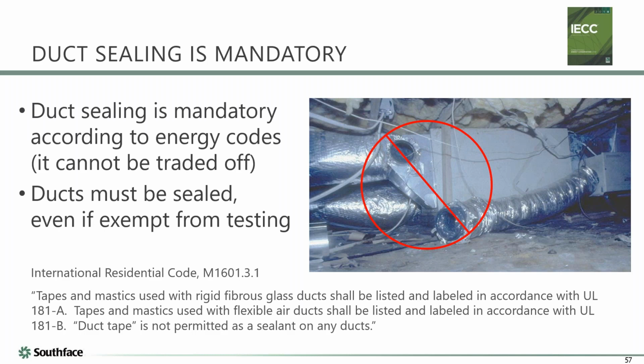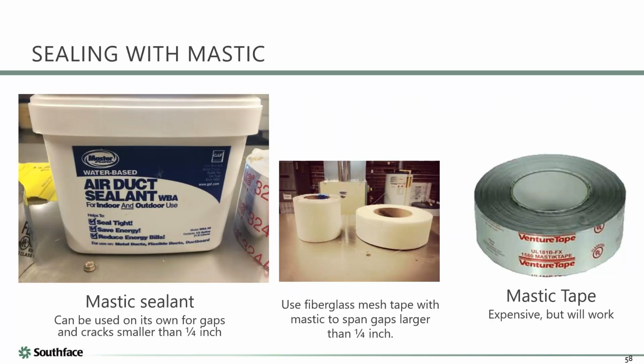I think we have some opinions about using tape as a sealant. Here they used tape as a sealant and it did not work. The code actually says you may use UL 181 listed tape or UL 181 listed mastic, and they do not allow what they call classic duct tape. So here's a picture of mastic. This is the material that we definitely endorse. I use it for a lot of other projects.